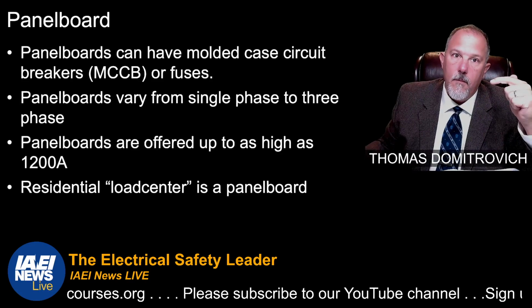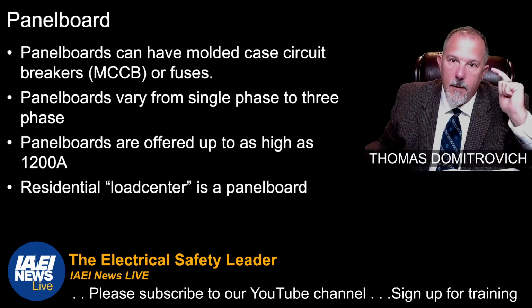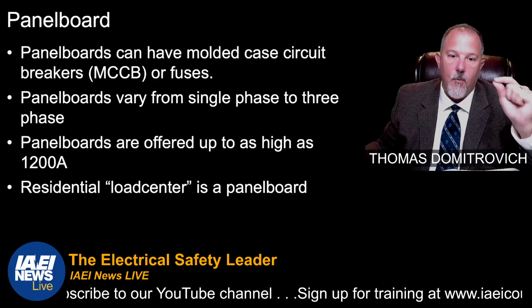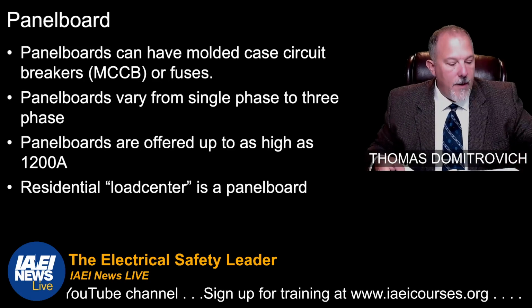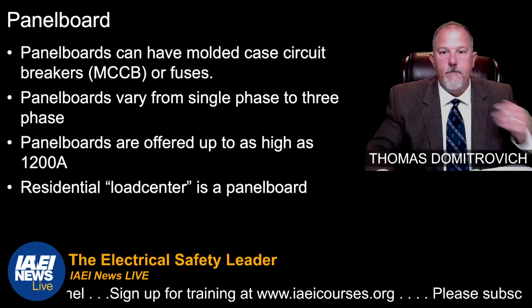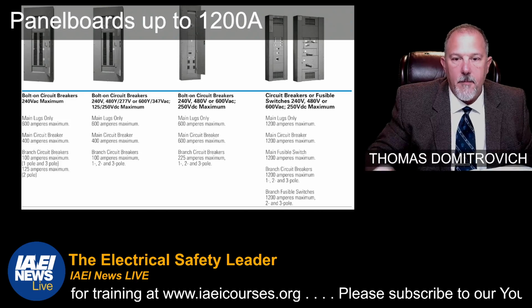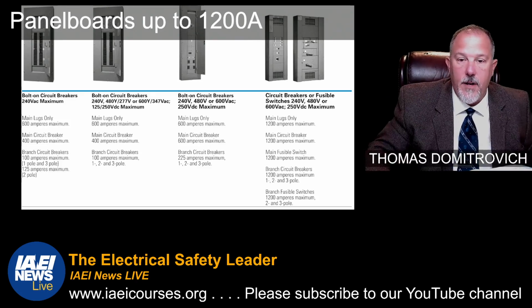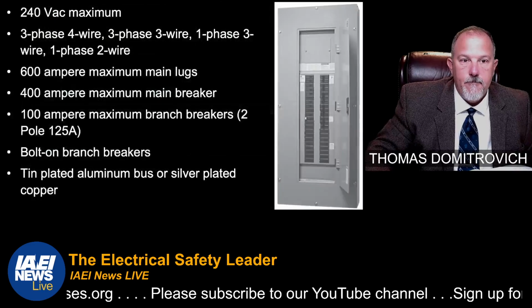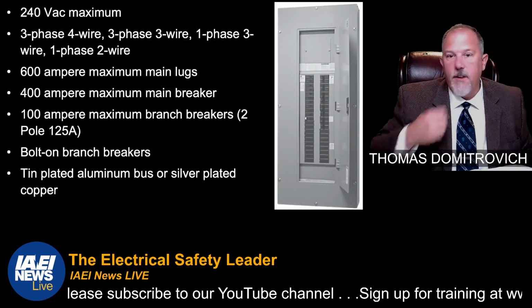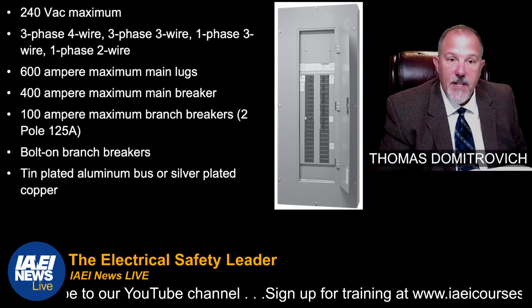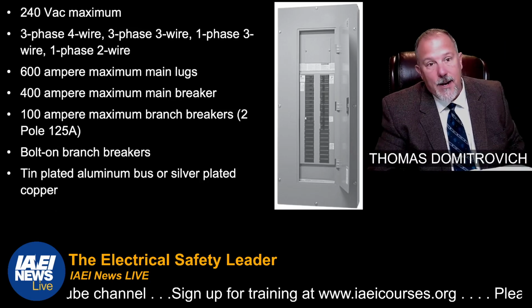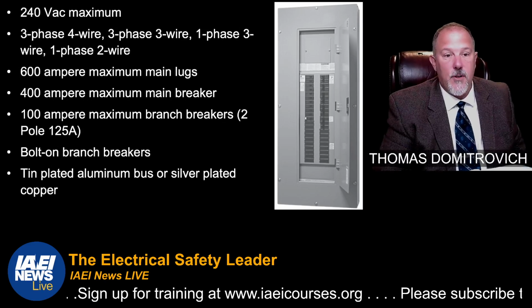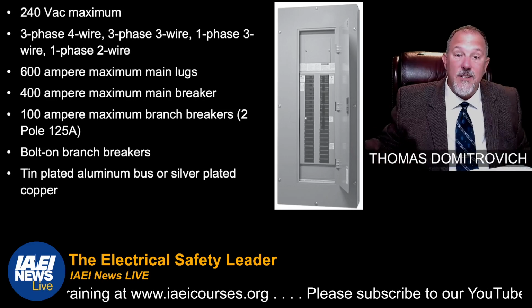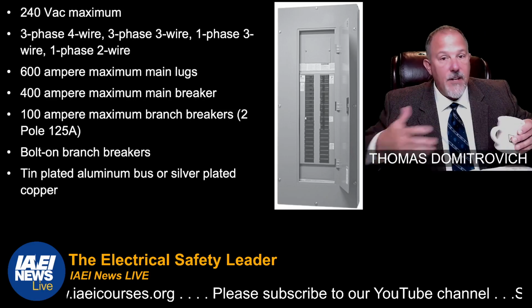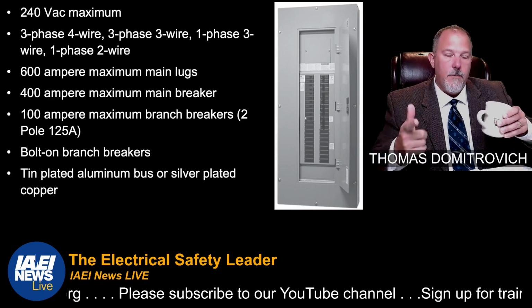So panel boards and load centers are one and the same. And you can go up to 1200 amps in a panel board. Those are big ones. Main lug only, 1200 amps, main circuit breaker, 1200 amps, all that good stuff. This is an example of a 240 volt maximum panel board. 3-phase 4-wire, 3-phase 3-wire, single-phase 3-wire, 600 amps, 400 amps, 100 amps, bolt-on breakers, tin-plated aluminum bus, or silver-plated copper. So many manufacturers will have different arrangements. Now, well, we'll get to it. All right.